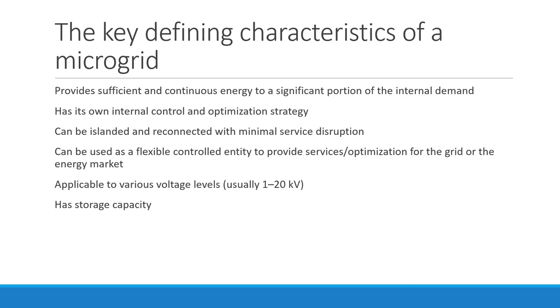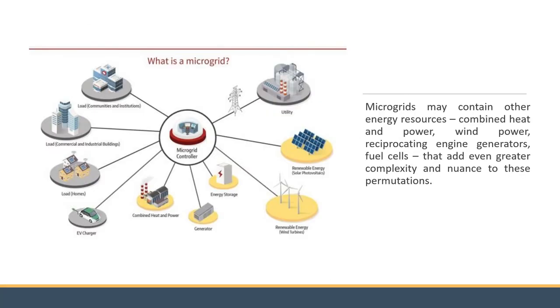The other characteristics which define the microgrid: it provides sufficient and continuous energy. It should have its own internal control and optimization strategy. It must be able to operate in islanded mode and able to reconnect to the main grid. It can also be used as a flexible control. It is also applicable to various voltage levels, usually 1 to 20 kV, and it may have storage capacity.